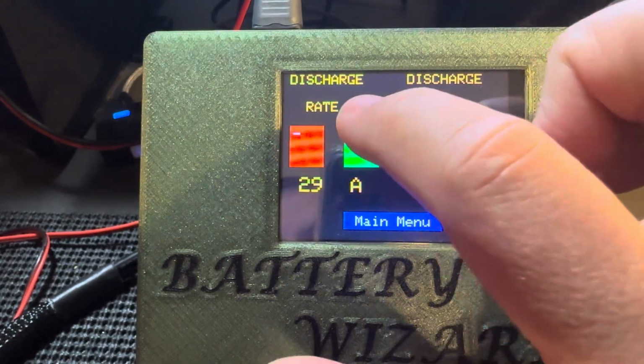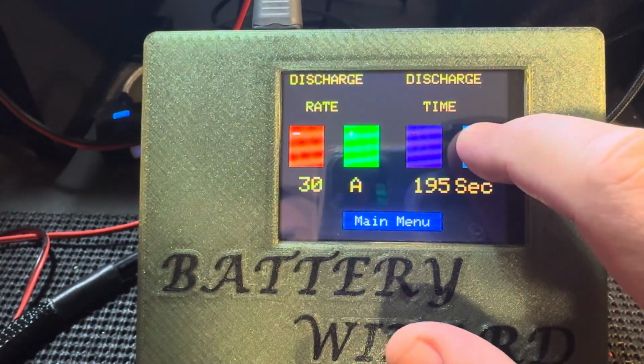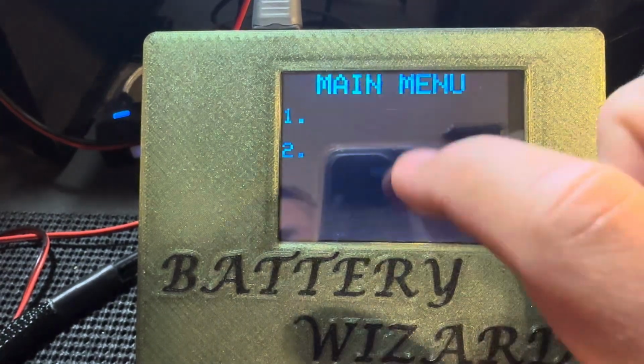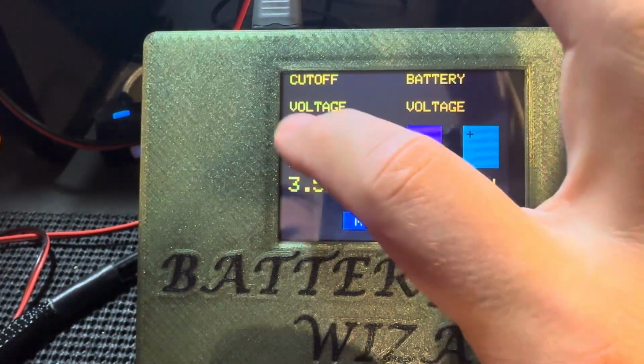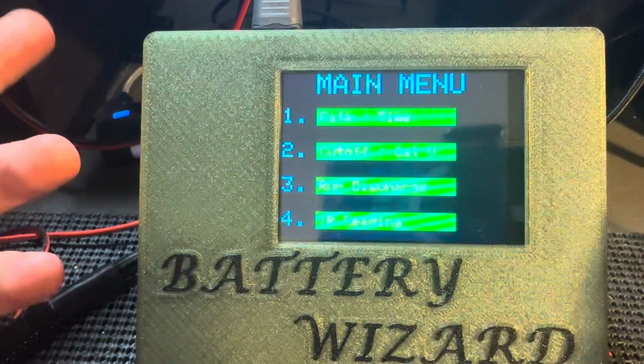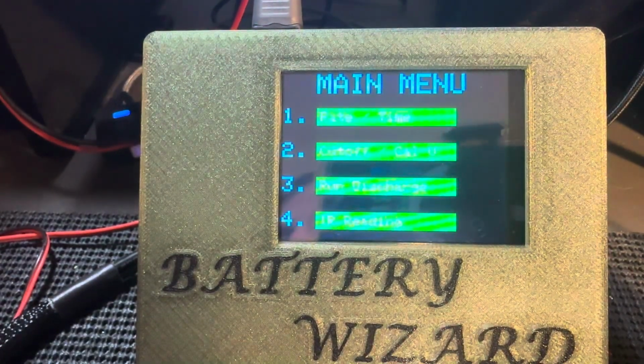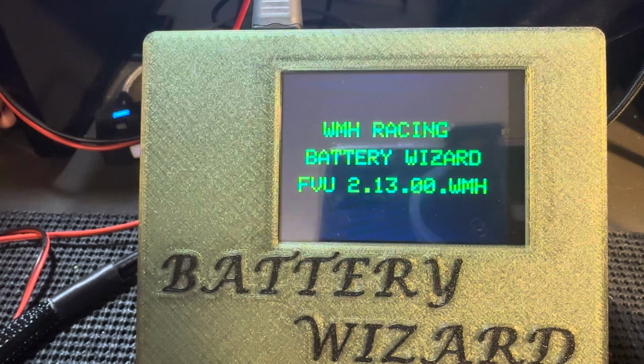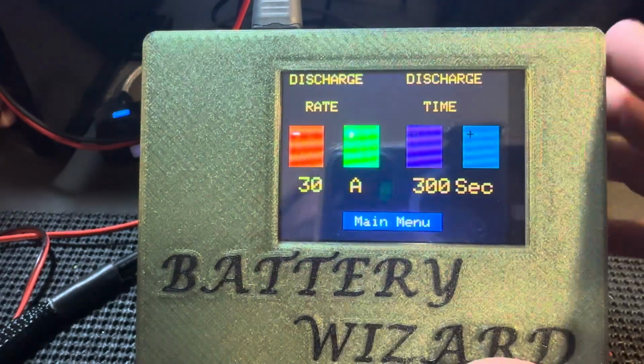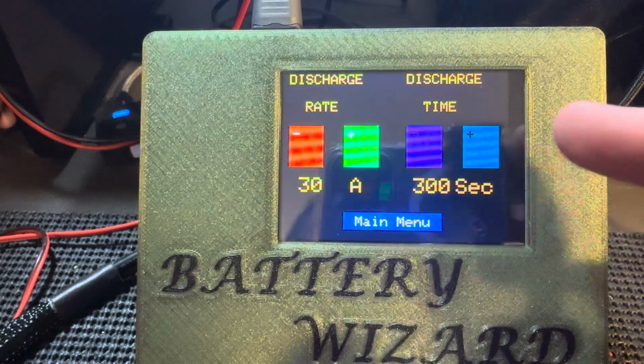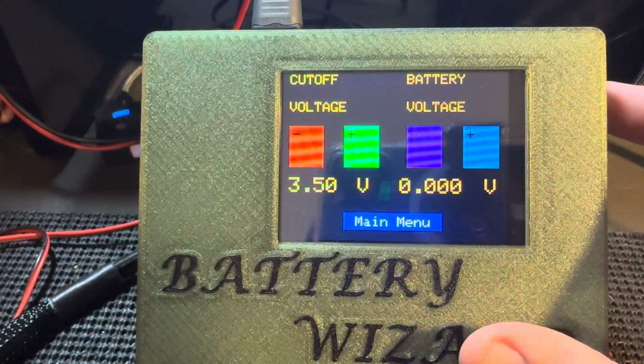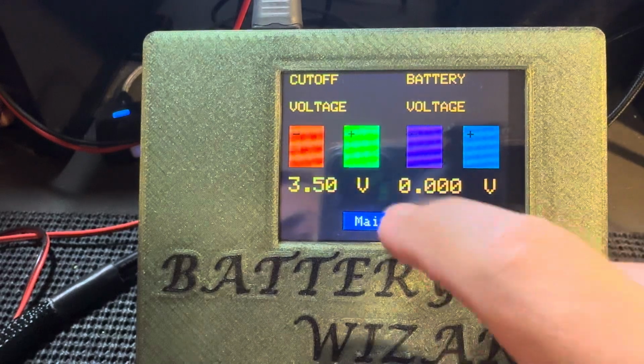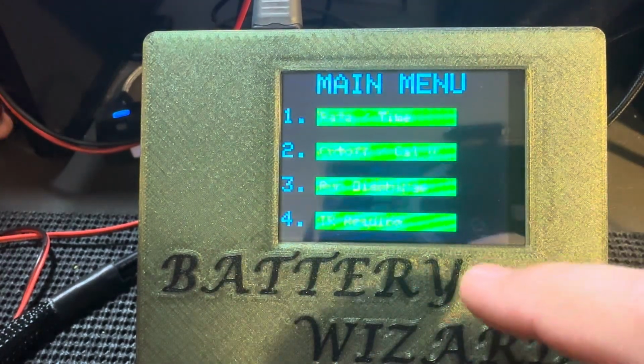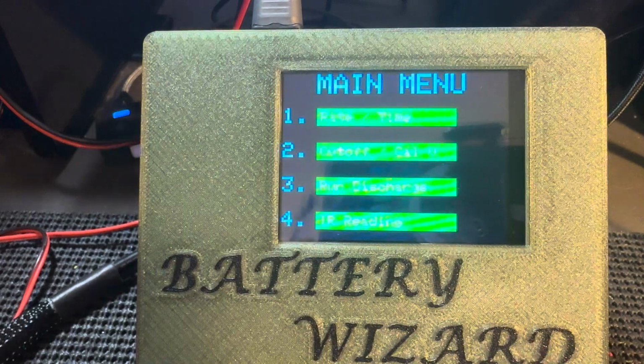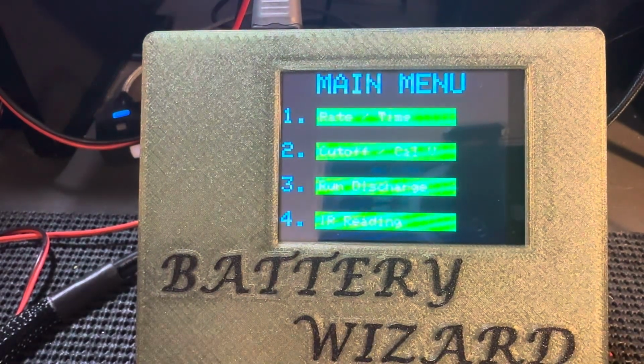Now if I move this up to, say, 30 amps, set this over to 300 seconds for a 5-minute discharge, and bring the cutoff voltage down to 3.5 volts, then exit out and power the Battery Wizard off and back on, you'll notice that all that information is saved - 30 amps, 300 seconds, and the cutoff voltage 3.5 volts. So those settings will be saved upon exiting that menu for the next time you want to use the Battery Wizard.